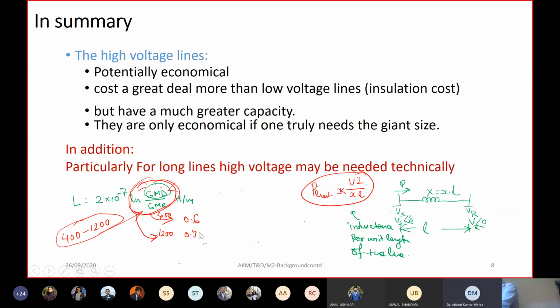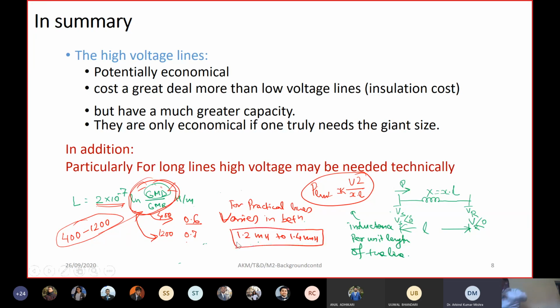So what does it mean? That inductive reactance, if you multiply this quantity by this, the inductive reactance for all practical lines varies in between 1.2 millihenry to 1.4 millihenry. Not much variation. You have taken so many cases, stranded conductor, solid conductor, bundled conductor, and so on. So even assuming inductance as a fixed quantity, if you cannot calculate it, it is not a big deal. Now you might think the teachers have made a fool of me.